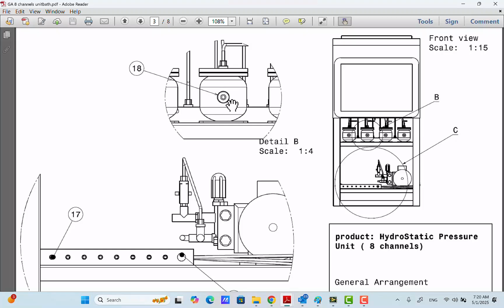If you buy this kit from the local market, you can change the pressure inside the accumulator anytime it is needed. This is a standard connection for the accumulator, and you can easily change the pressure using the air pressure line of your factory. If the required setting pressure for the accumulator is less than the compression line of your factory, of course you can use air. For higher pressures, you can use nitrogen balloon gas. That is the standard procedure for charging the accumulators.